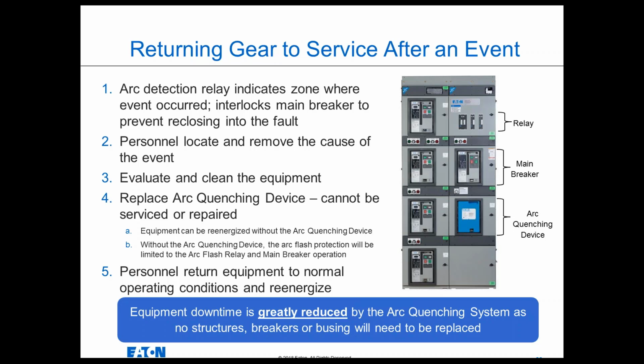So in the event of an arc flash, another benefit of the wired point sensors is that they will indicate the location of where the fault occurred inside the switchgear, because the relay knows which sensor saw the light, so it'll be able to direct you to where in the switchgear that fault occurred. So personnel would locate and remove the cause of the event, they'd evaluate and clean the equipment. The arc quenching system operates so fast that it does protect the equipment from damage. It should still be inspected just to ensure that there was no damage. And if there is any minor damage, it should be repaired.